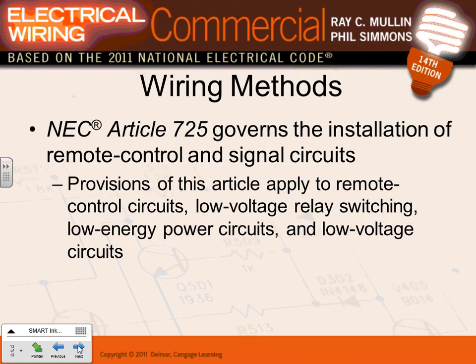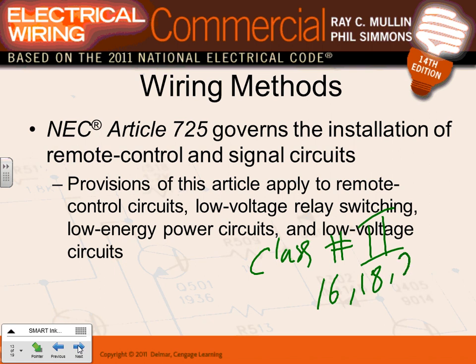Now, in terms of wiring, the code considers these class 2 wires. Class number 2 wiring. Class 2 wires, you can typically use 16, 18, 20 AWG, not a whole lot. Now, can I use number 14? Yep. We'll be overkilling a little bit. So you can use them.